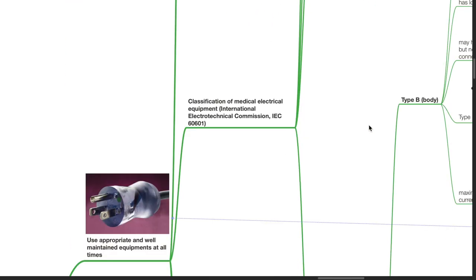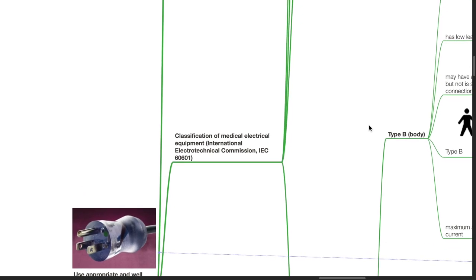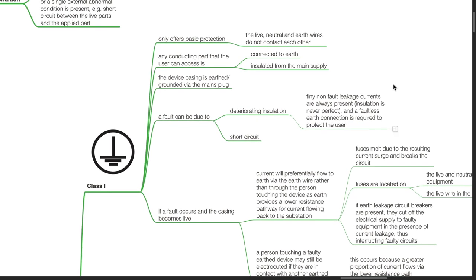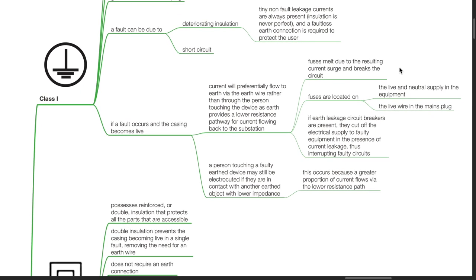Classification of Medical Electrical Equipment according to IEC 60601-1. Class 1 equipment offers basic protection where live, neutral, and earth wires do not contact each other. The device casing is grounded via the mains plug. A fault can be due to deteriorating insulation or short-circuit. Tiny non-fault leakage currents are always present as insulation is never perfect, and a faultless earth connection is required to protect the user. If a fault occurs and the casing becomes live, current will preferentially flow to earth via the earth wire rather than through the person.